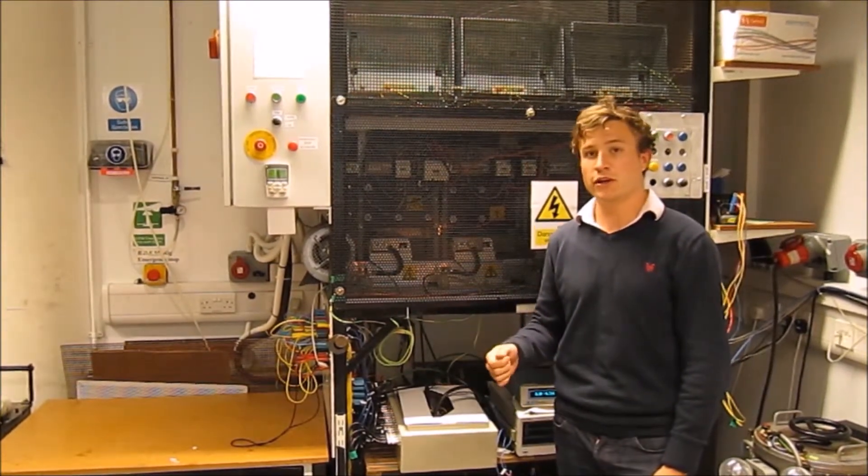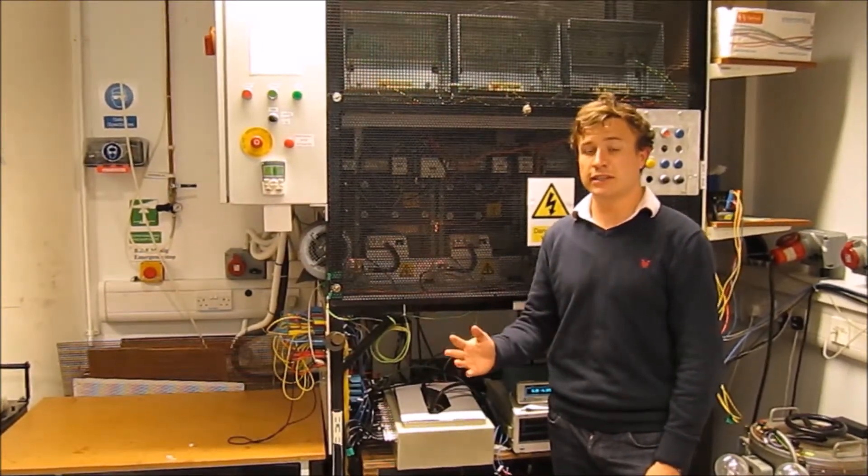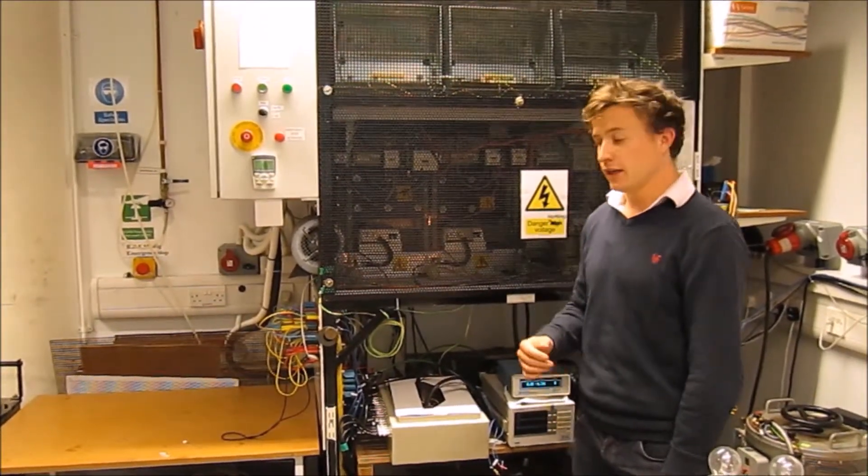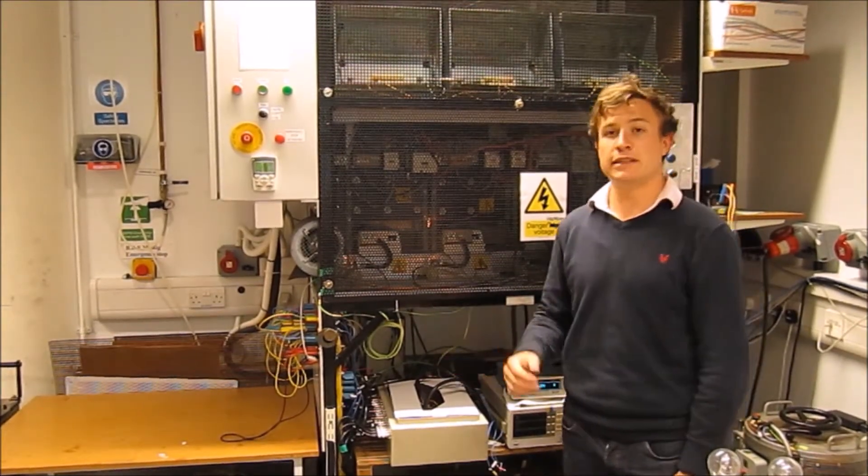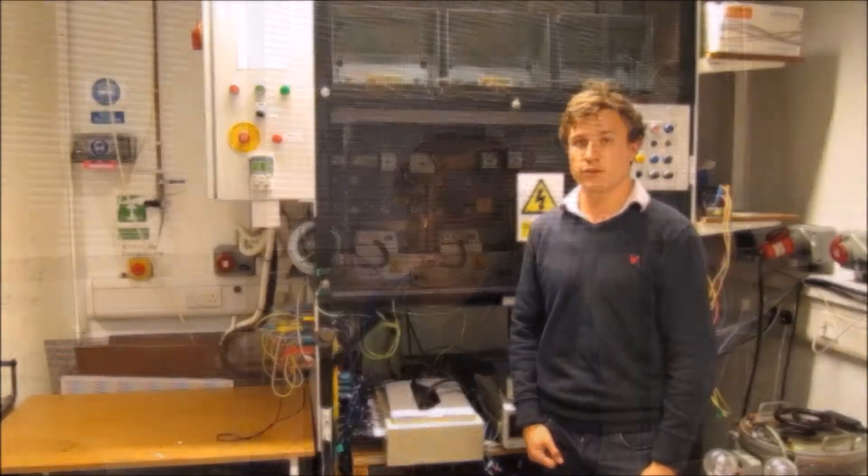We had three different controllers. One was to test the grid synchronization of the machine, another to test the real and reactive power of the machine, and finally to test the machine's ability to ride through low voltage faults.